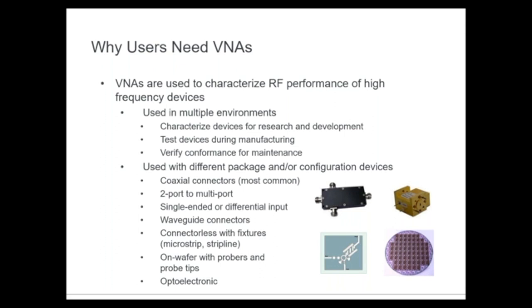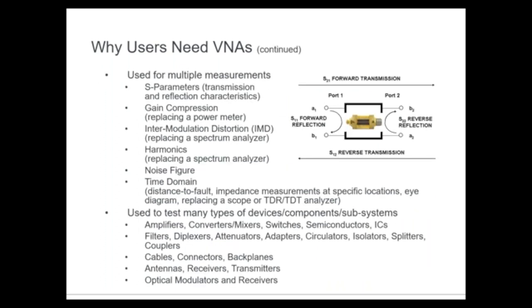We have various methods to transfer the reference plane of our measurement to where we want it, so we're measuring just the device. Most commonly we have coaxial devices — two-port, multi-port, differential inputs, single-ended, waveguide devices, fixtures, probe stations for semiconductor wafers, and even optoelectronic cross-domain measurements like E-to-O and O-to-E, measuring optical modulators, receivers, and transceivers using an electrical VNA. The basic measurements are S-parameters: forward and reverse transmission, forward and reverse reflection — those are your four S-parameters for the two-port case.